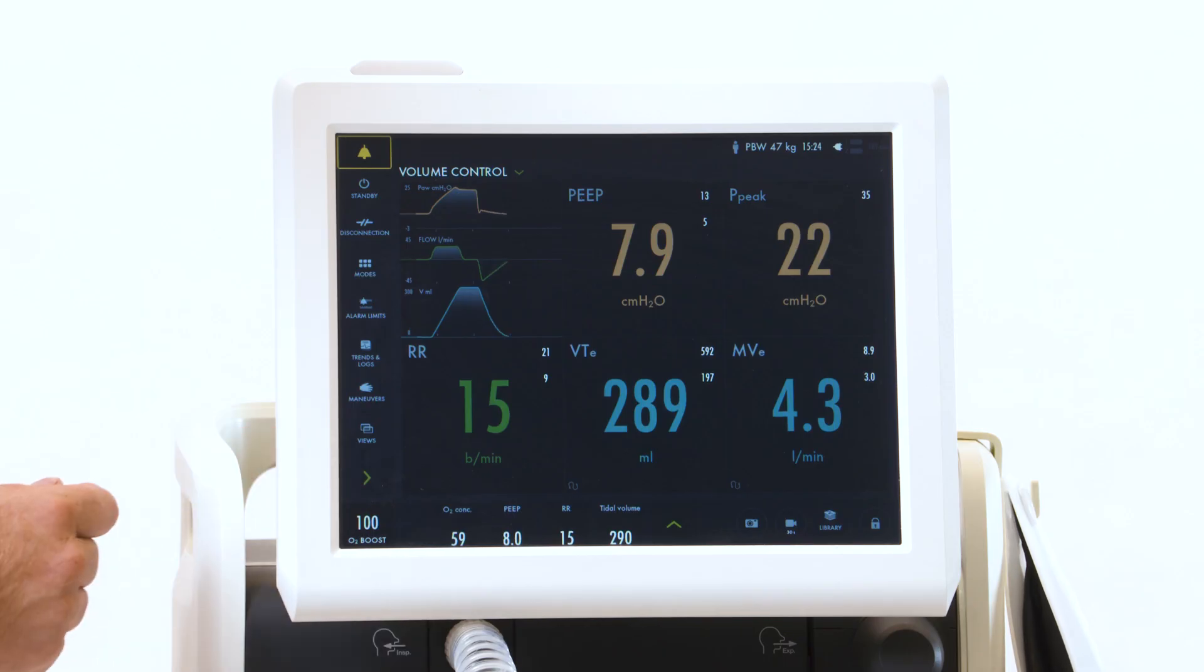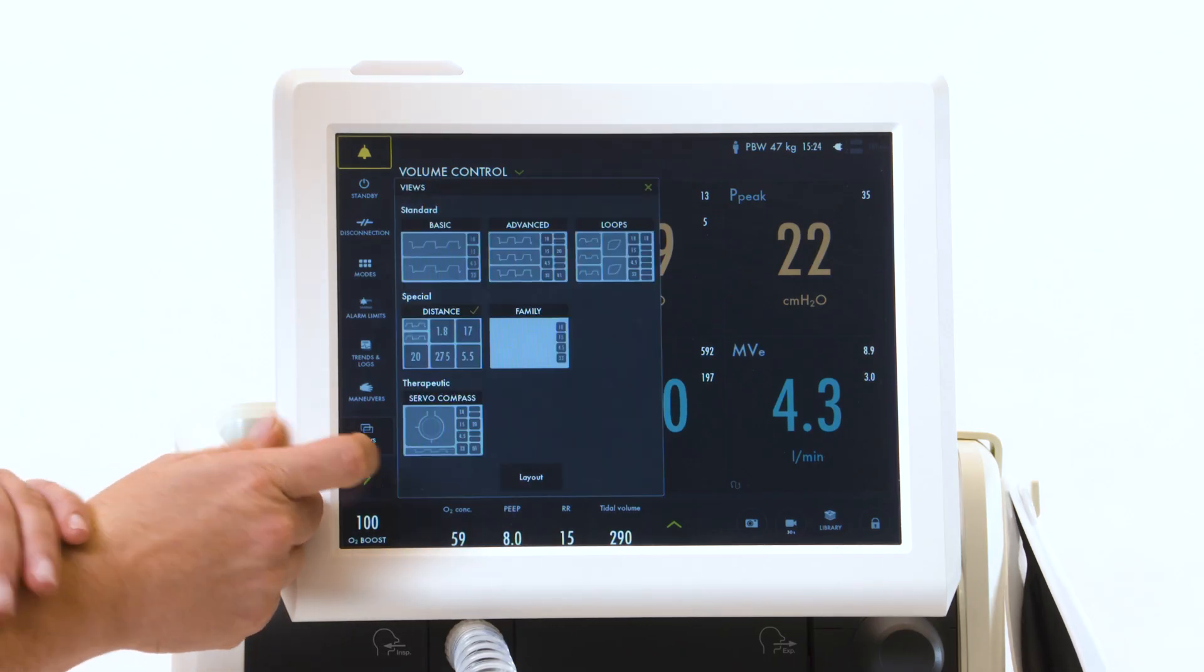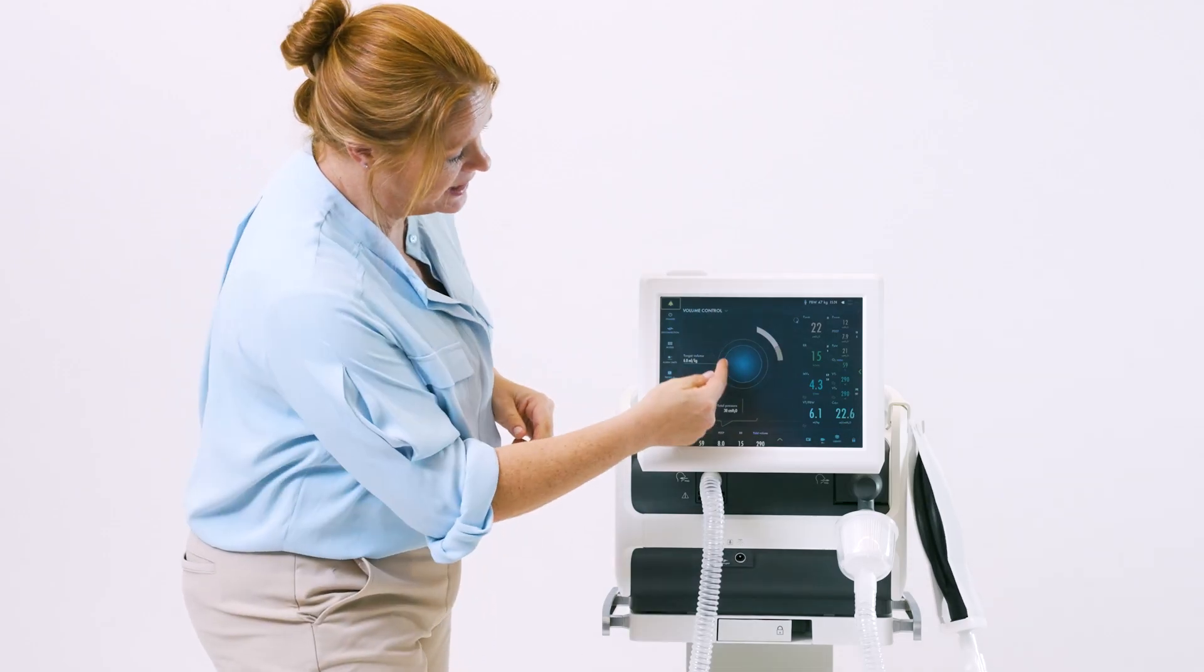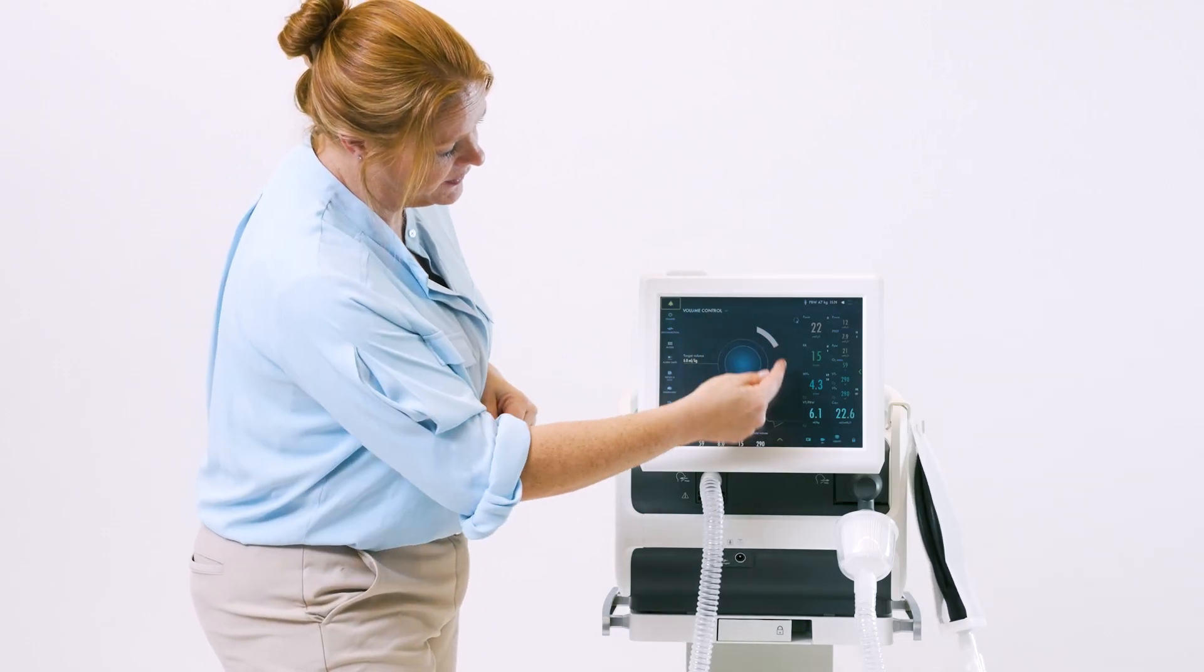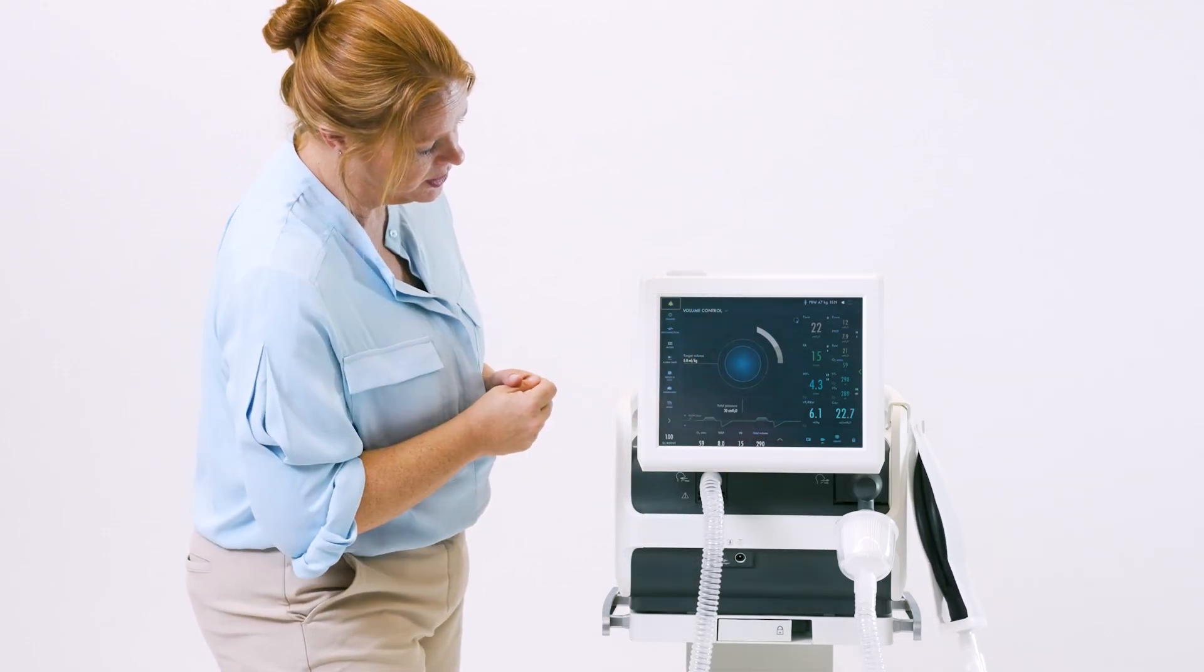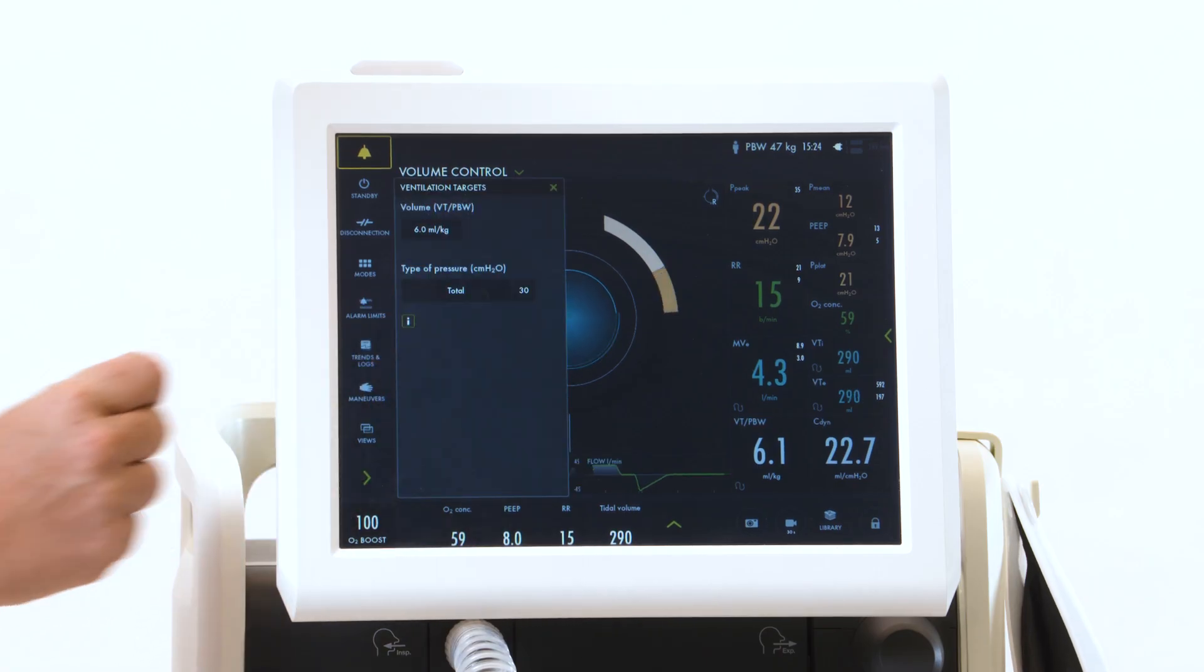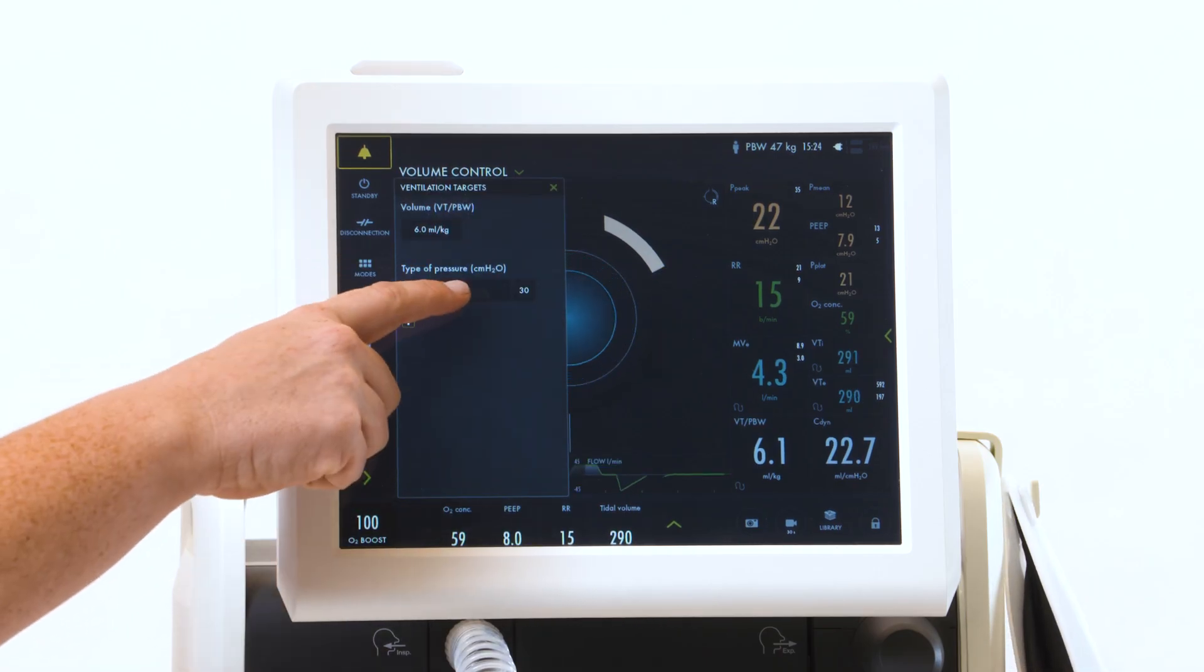Your last and final view is ServoCompass. ServoCompass is a snapshot looking at volume and pressure based on your settings. The inside being volume and the outside being pressure.